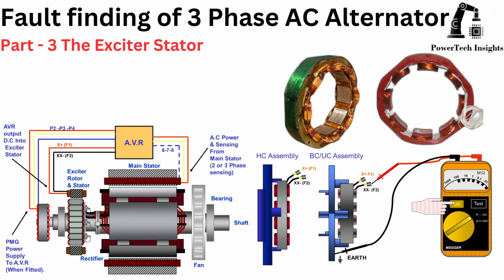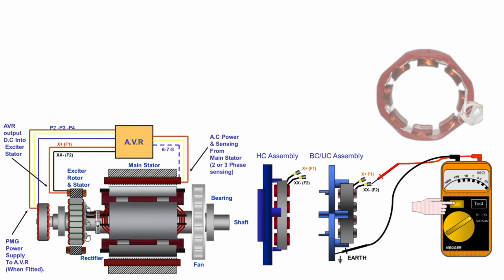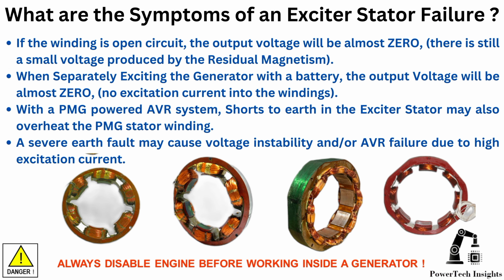Part 3. The exciter stator. In this part, we will provide a comprehensive guide on fault diagnosis for the exciter stator. Let's get started. Possible symptoms of an exciter stator failure. If the winding is open circuit, the output voltage will be almost zero, but there is still a small voltage produced by the residual magnetism.